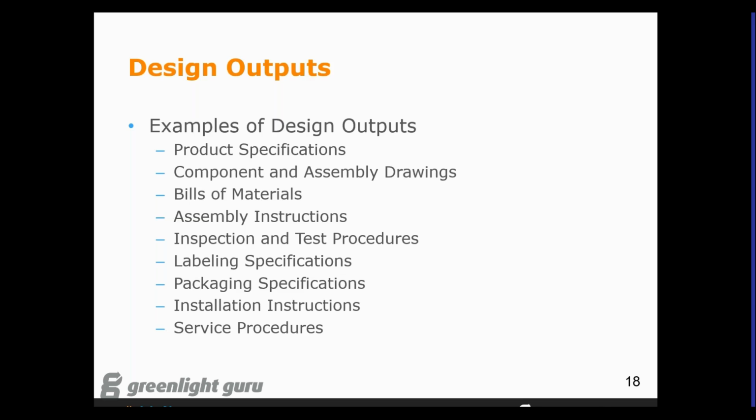Then there will be a little bit more variability on how they go about documenting assembly instructions, test and inspection procedures. And I've seen a number of organizations that don't really pull into the engineering product specification some of the labeling, some of the packaging, and even more remote would be some of the installation and servicing documentation.